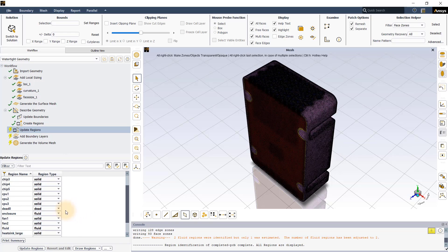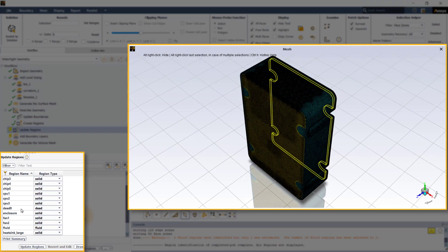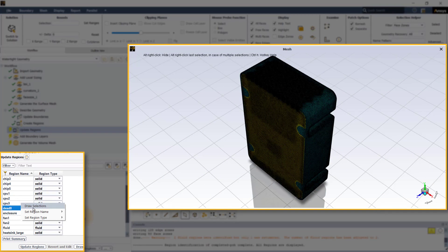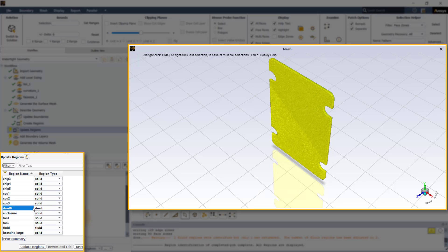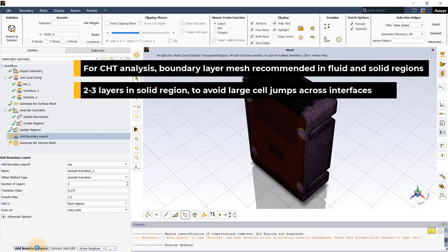The enclosure can be changed to solid region type in the update regions task. Also, the workflow automatically detects the void region which is assigned the dead region type. Since our aim is to generate a mesh for conjugate heat transfer analysis, it is generally recommended to add boundary layer mesh even in the solid region, in addition to the walls in the fluid region, to avoid large cell jumps across solid-fluid interfaces.